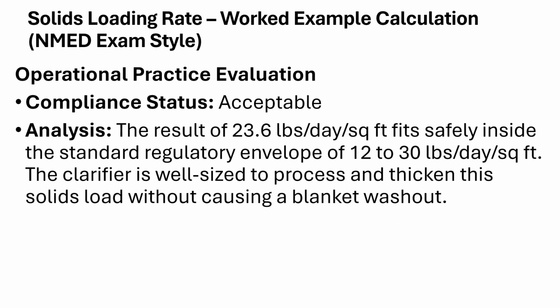Okay, so let's evaluate this. That 23.6 pounds per day per square foot, it's acceptable because remember, our range for a secondary clarifier is 12 to 30 pounds per day per square foot. So we're in the middle of that. We're not in the high end, we're not in the low end, we're right in the middle of it. So the clarifier is well sized. It's appropriately sized to thicken the solid load, and it won't cause a blanket washout. So that's what we're looking at.